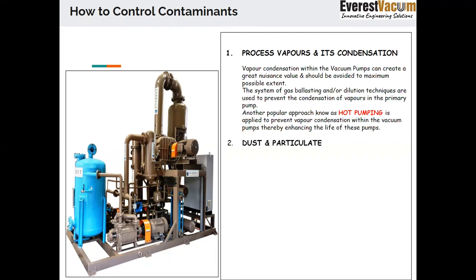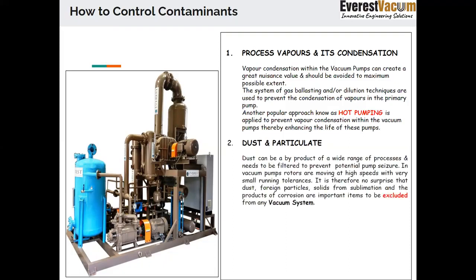Now, another problem arises from dust and particulate matter. There are certain processes wherein these contaminants, these particles, would enter the dry screw vacuum pumps. So we need to ensure that we have certain traps and filters in position so that they do not directly enter the dry screw vacuum pump.